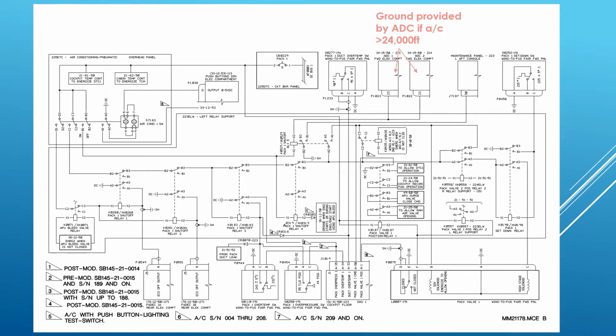The other relay, relay number 4, is basically linked into the engine start system. So what we said is during engine start, if we're using APU air, both packs shut down. If we're using the engine to start the other engine, the pack on the engine that's being started shuts down. That's basically being controlled by relay number 4. It gives you the logic in that little box there as to when it energizes or not. There's no latching circuit, so once the start cycle is finished, it goes back to normal. It just resets, and then the pack will come back online.